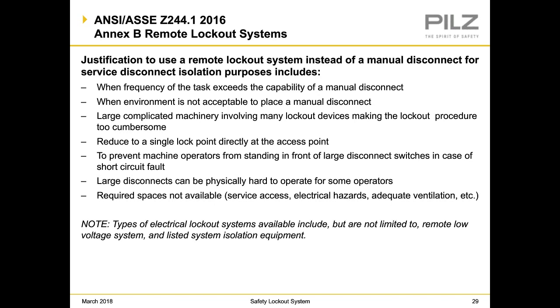Some larger disconnects can actually be pretty hard to operate, and if they're doing that multiple times a day, that's not necessarily a task that operators really should be doing. Required spaces are not available, so service access, electrical hazards, adequate ventilation might not be available. So these are some of the reasons that electrical lockout systems can be used.